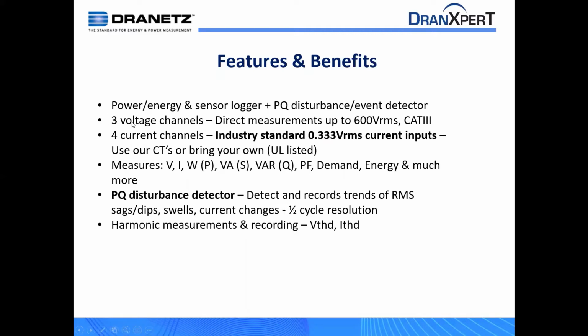Primarily, there are 3 voltage channels for direct measurements up to 600 volts AC, 4 current channels. So it's 3 primary phases plus the neutral. And we use industry standard 333 millivolt current inputs. And all of our CTs are compatible with that. Anything that we provide is UL listed and CE compliant. However, it does give you the ability to bring your own CTs if you wish to do it. But we do recommend that they are safety approved for your own benefit here.